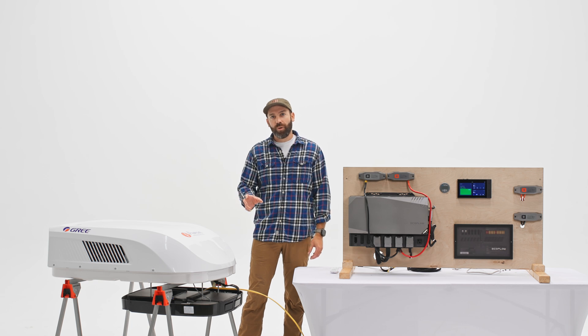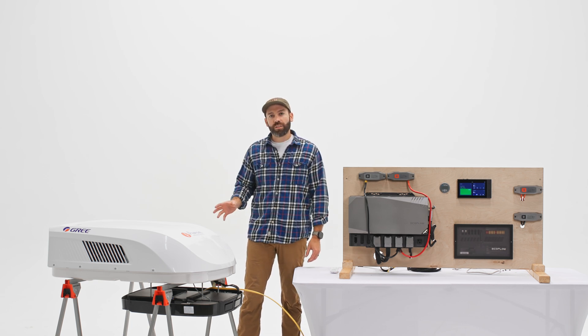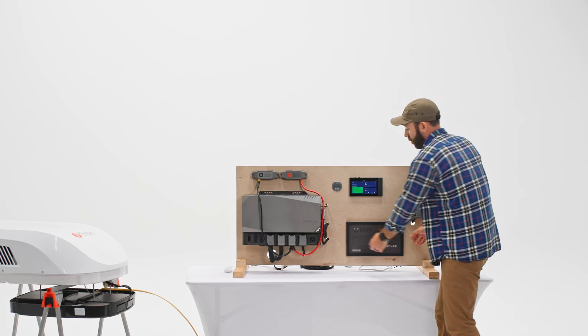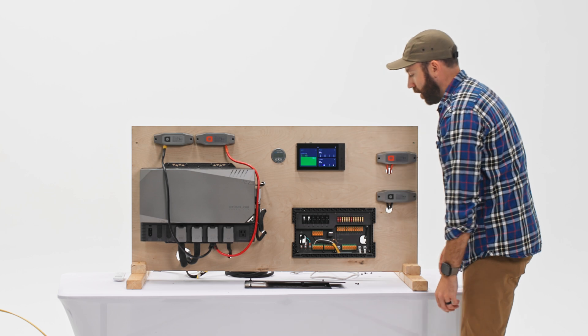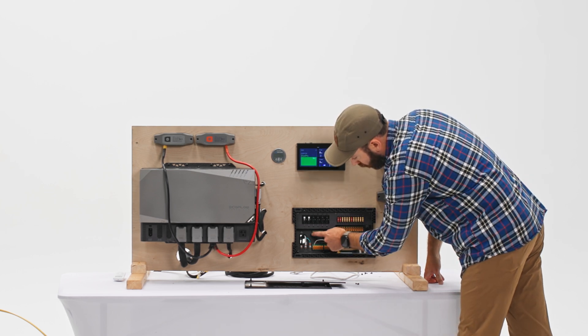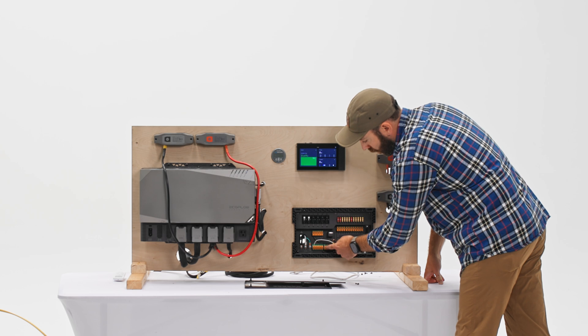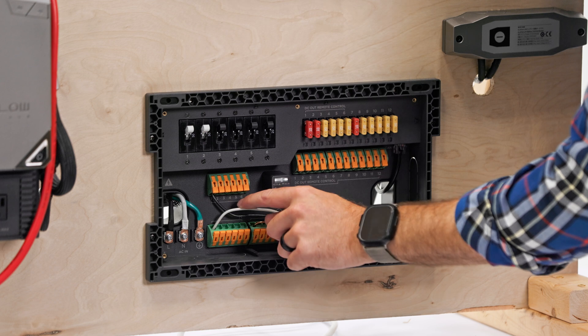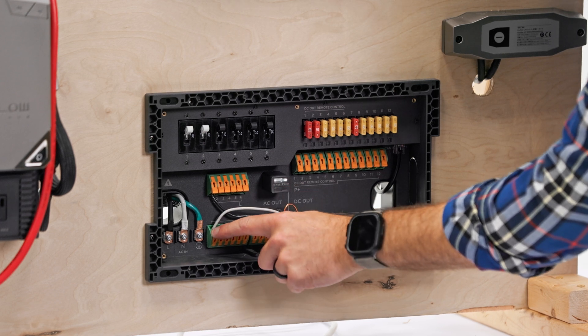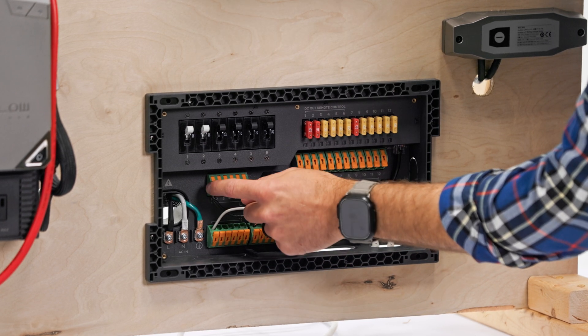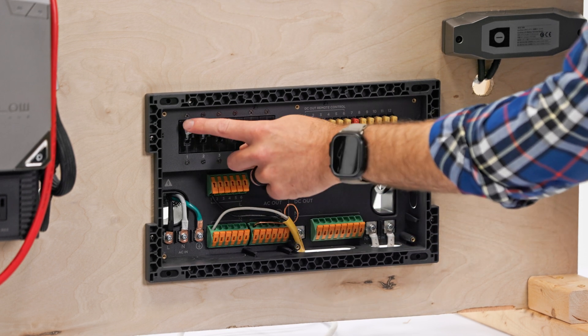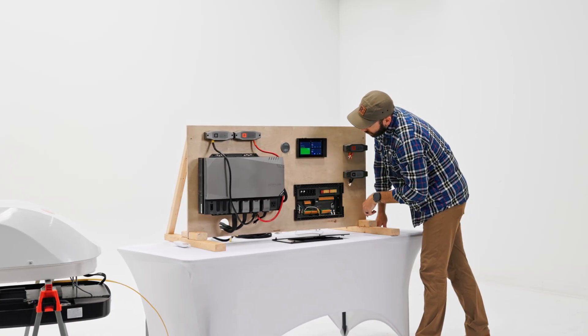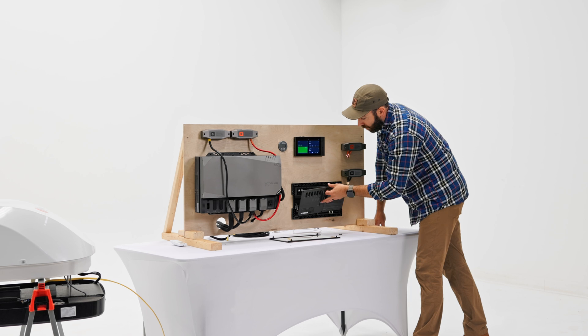All right, so we've got our unit wired in here into our distribution panel. I'm going to quickly pop off the cover. So we've got our 12-2 Romex coming in here. We've got our load on the top, our neutral, and then our ground bar. So our ground is coming into the ground, we've got our neutral, our white wire here into position one, and then our load black wire coming in also into position one. So that's going to be this first breaker here, this is a 30 amp breaker, and then our AC output is on.